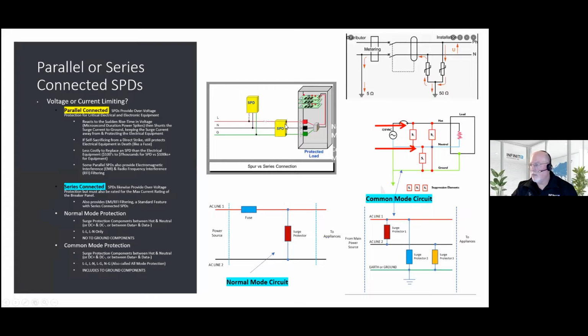So instead, we have parallel connected surge arresters. A parallel is connected to a dedicated breaker in the breaker panel, and then it protects the loads on that panel. And if this thing fails, you just secure the breaker to the surge arrestor, not to the whole building, and you can replace it or do maintenance on it. You wouldn't have both, but later on, you'll see why you would want both. So this is here visually just to show you the differences.